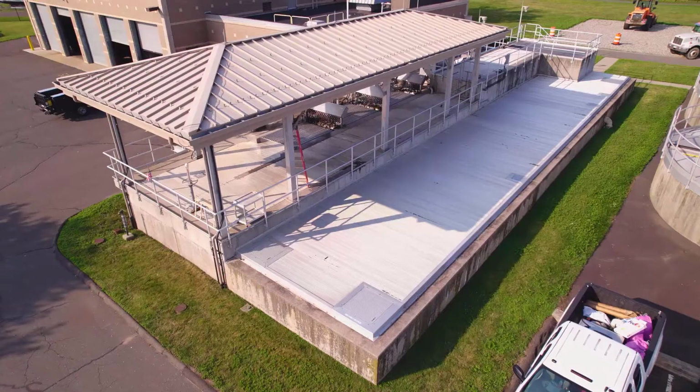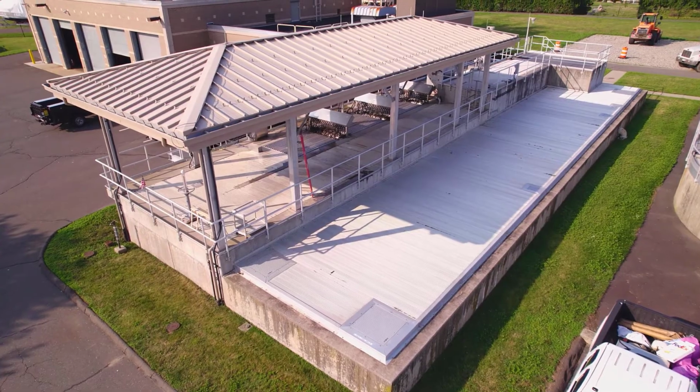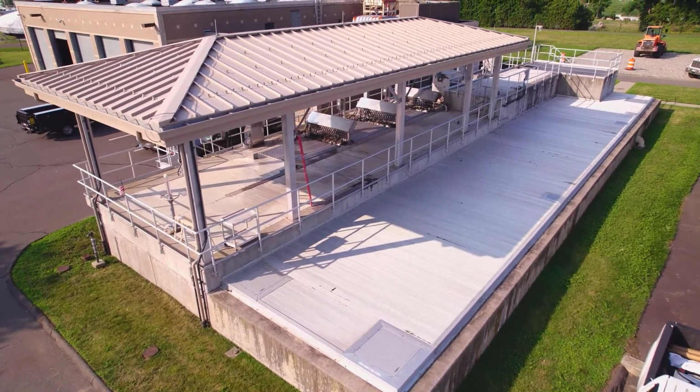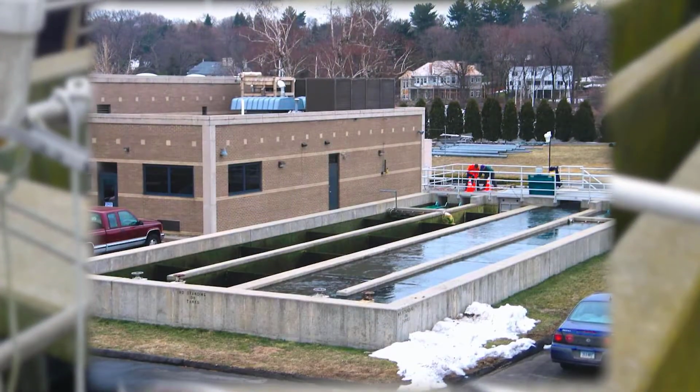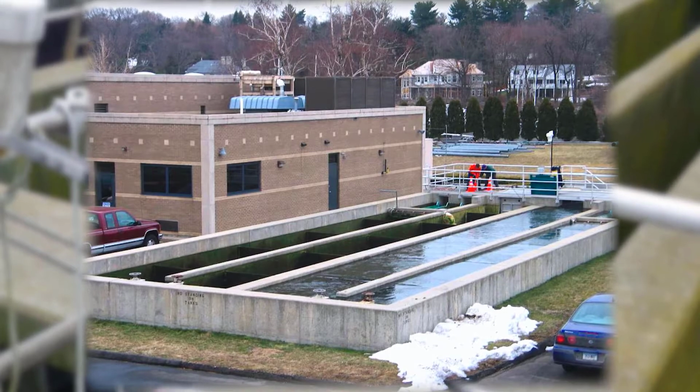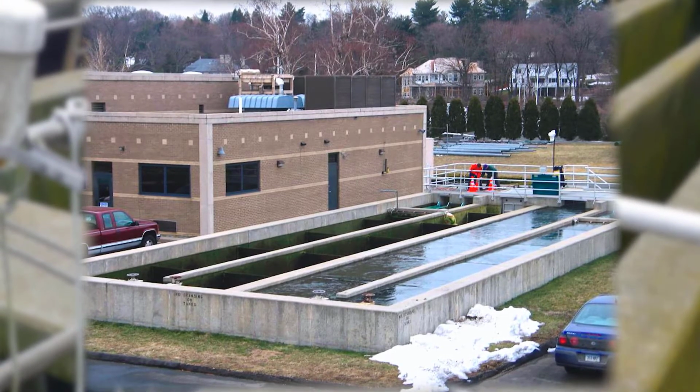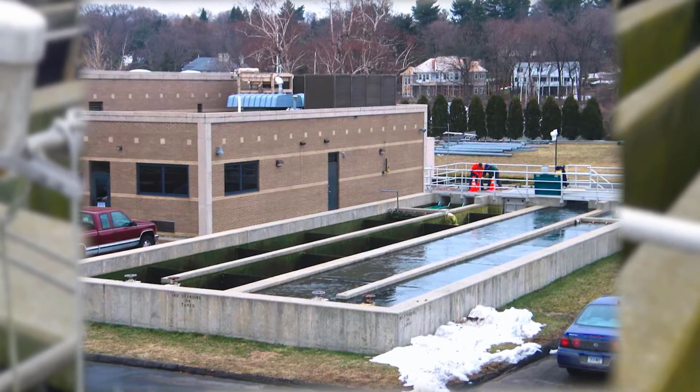Sewage treatment plants in the U.S. typically use chlorine or ultraviolet radiation as methods of disinfecting the final effluent. Chlorine is the most widely used disinfectant for municipal wastewater systems. It destroys pathogens by oxidizing cellular material and is effective against a wide range of organisms.